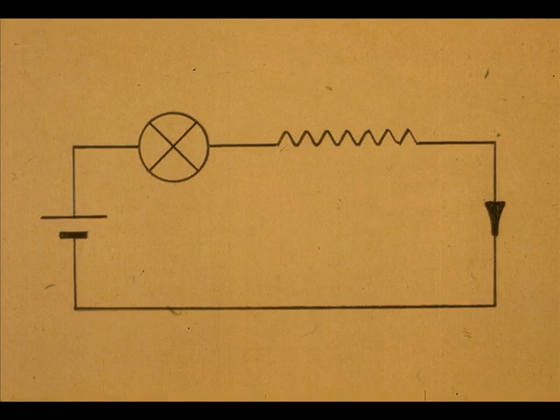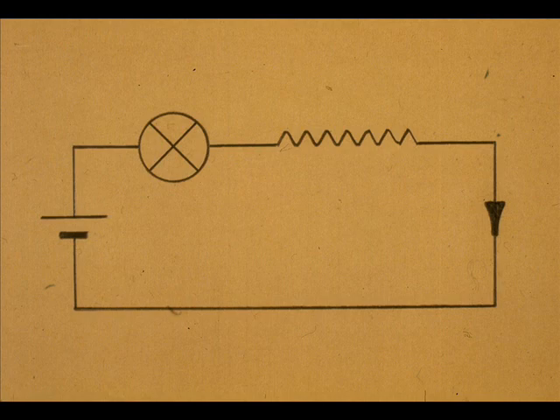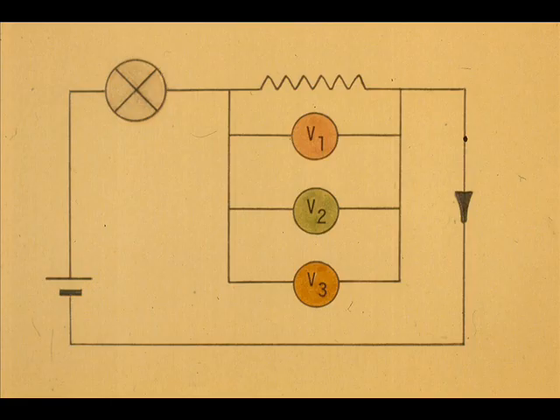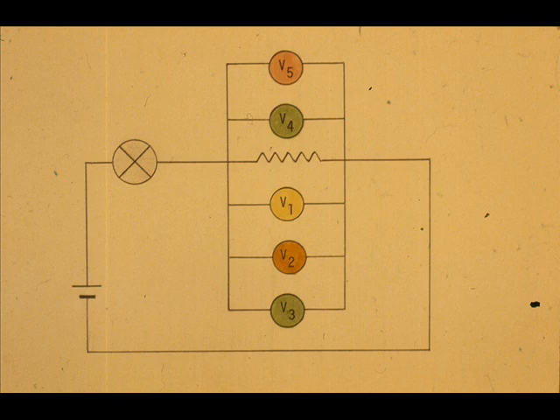The parallel system can also be compared to a battery and resistor circuit, but with only one resistor in the loop. Controllers, alarms, and other components are essentially voltmeters hooked in parallel across the one resistor. This resistor section is commonly called the input module. Loop resistance is not affected by the addition or deletion of components, due to the high input impedance of the recorders, controllers, alarms, and other items placed in parallel with the input module.